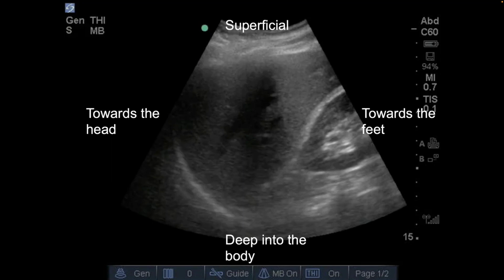And again, just to reiterate here, you can see the dot is in the top left-hand corner of the screen. That correlates with the bump on the probe, and that's always going to be towards the patient's head. For this orientation, again, just so you know what you're looking at, the probe is up here at the top where it says superficial. So this would be the skin that you're shooting through, the subcutaneous fat. Then you get to the liver. And the further you go down is the deeper into the body that you're looking, okay?